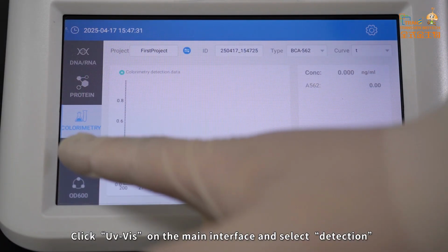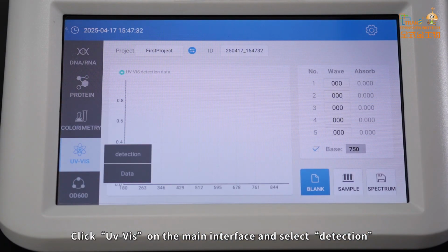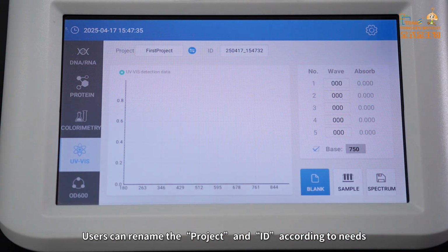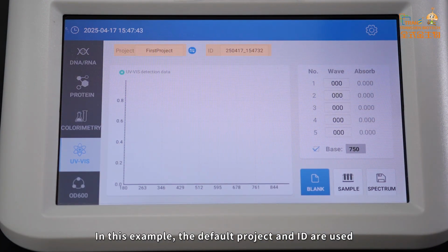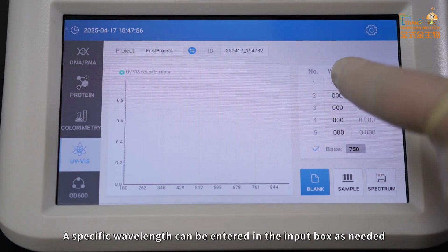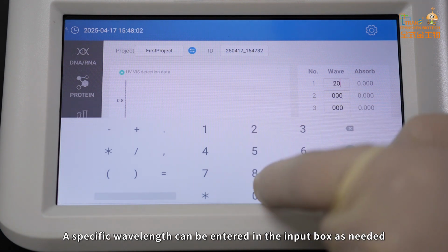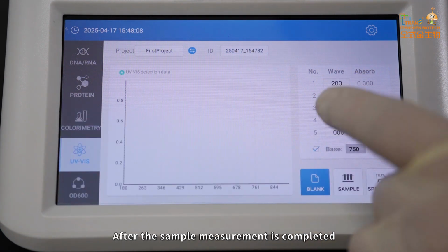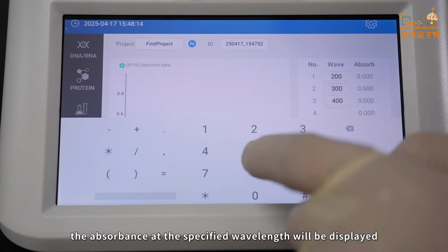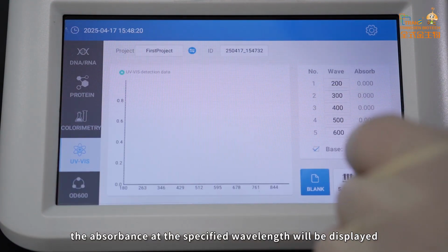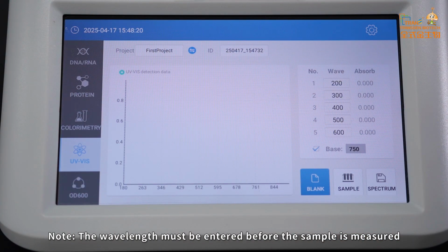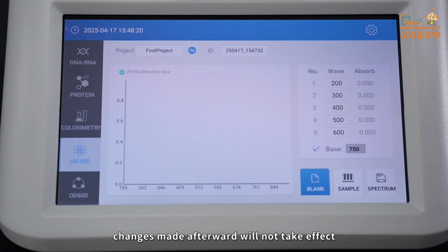Click UV-Vis on the main interface and select Detection. Users can rename the project and ID according to their needs. In this example, the default project and ID are used. A specific wavelength can be entered in the input box as needed. After the sample measurement is completed, the absorbance at the specified wavelengths will be displayed. Note: the wavelengths must be entered before the sample is measured. Changes made afterward will not take effect.